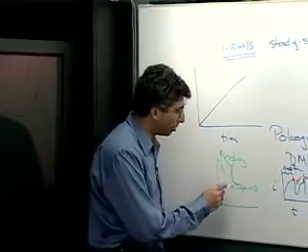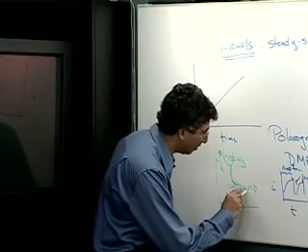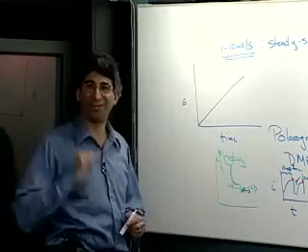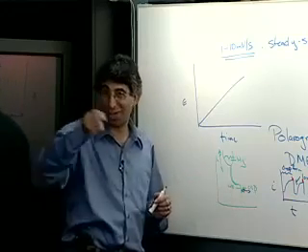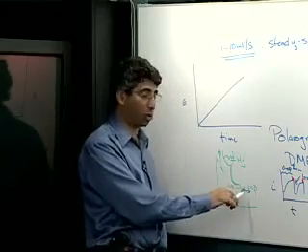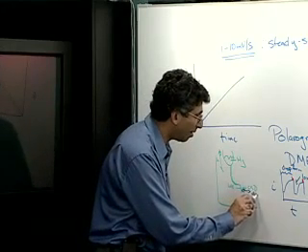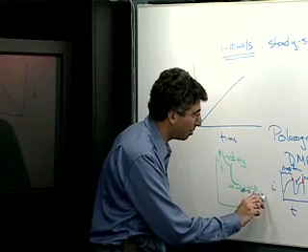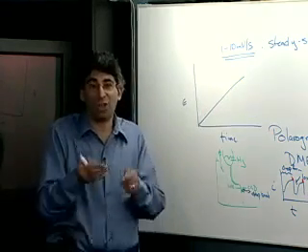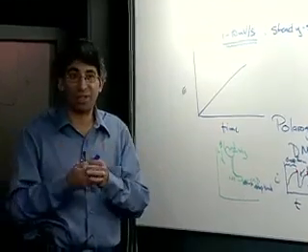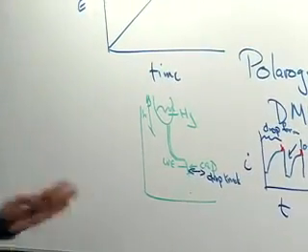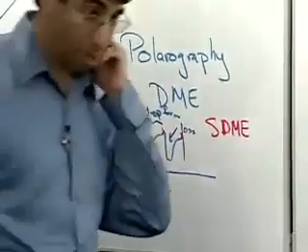And a drop knocker is just a little piston-like thing, a little tapping device right here that goes and taps the end of your capillary, or shakes it, depending how you want to think about that. And every time it shakes it, a drop falls off. And of course, since you're controlling this now, you can knock a drop off once every second or whatever. And as long as you pick a time frame that is faster than the natural falling off rate of the drop, you're in great shape. And now you get a very good reproducibility, and you can do things like sampled polarography.